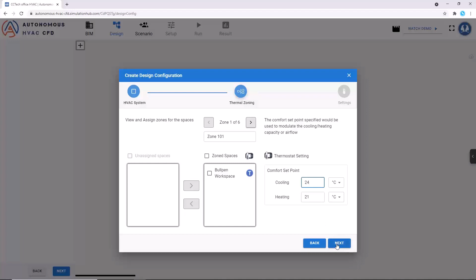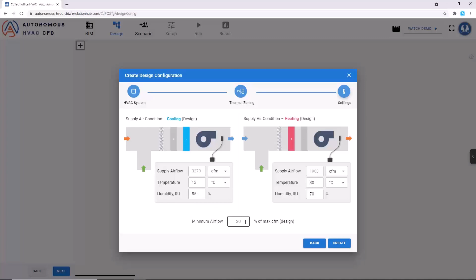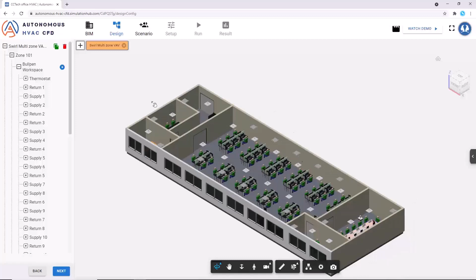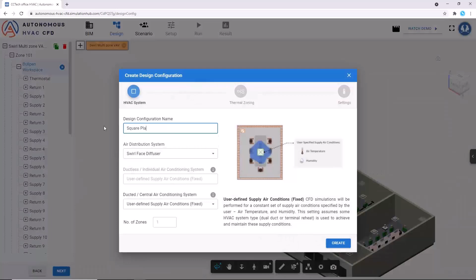In our case, I am selecting multi-zone VAV system with 6 zones. This means each space has its dedicated VAV box and thermostat settings. Now specify the supply air conditions like temperature and humidity as it leaves the AHU. The app shows the preview animation of supply flow from diffusers to assist the designers in validating their supply positions.